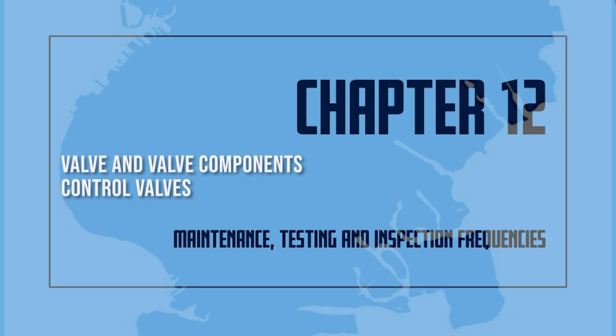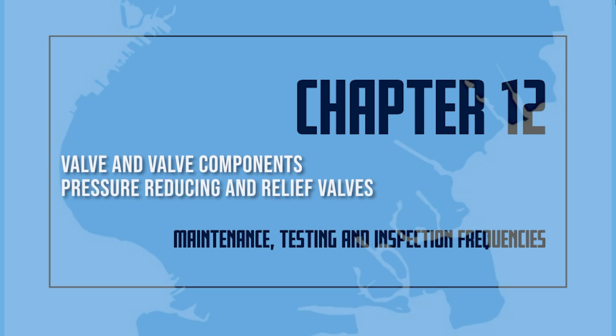All indicating valves controlling water supplies equipped with locks and/or that are supervised shall be inspected monthly. The inspection shall verify that the valve is in the normal open or closed position, properly sealed, locked, or supervised, provided with appropriate wrenches, free from external leaks, and provided with the appropriate identification. Pressure reducing and relief valves. Fire pumps. Casing relief valves.